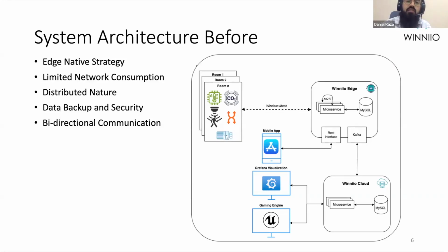And then the switch sensor that we have, this is placed on the windows and the doors in rooms to give us the indication if the window is open or if the door is open. And that will let us know like, okay, even if the actuator or the radiator is at 100% open and the room isn't getting warm, maybe the window is open too, right? So the heating system cannot do anything at all. We need some external help in order to close that window, because the windows are manual in the buildings that we are working with. If they are also automated, we can also potentially cover that ground with AI.